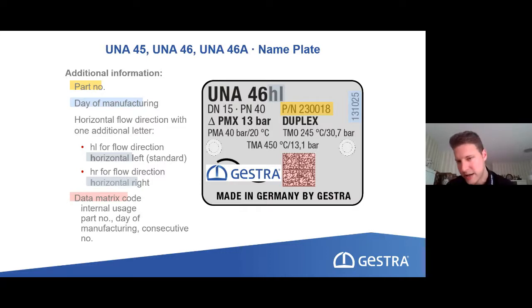We have 100% testing. So each and every ball float steam trap, UNA, will be tested, 100% testing. So we put pressurized air of 60 bar on the entry side, and we pull a vacuum on the other side, and the vacuum has to be stable, and only then we sell it and ship it.